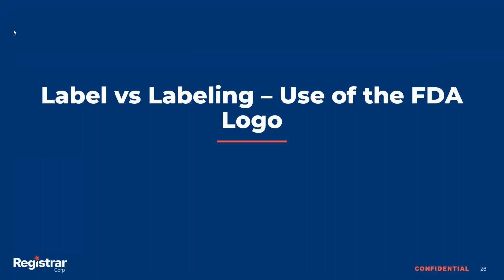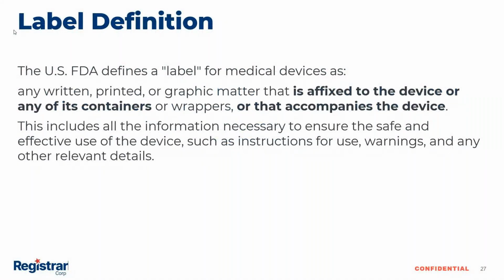So, label versus labeling, and use of the FDA logo. Oftentimes companies may get confused about what is considered a label and the labeling, or what the difference is between the two. Per FDA, a label is defined as any written, printed, or graphic matter that is affixed to the device or on its containers or wrapper, or that accompanies the device. So if you have a device, this label is affixed to the device or in the packaging. That includes all the information necessary to ensure the safe and effective use of the device, such as the warnings, instructions for use, or any relevant details.